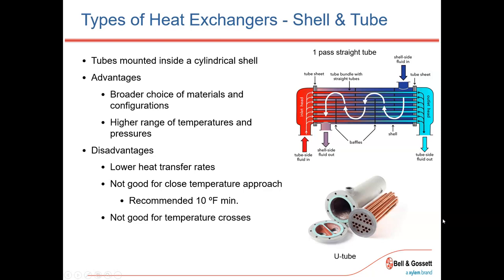And so it's great in that as you have extreme temperature differences between, let's say, your coil side and your shell side, the expansion and contraction rate won't match up, but that tube bundle is almost floating in there. So actually, take a step back. There are two different sides. You have the fluid that's within the tubes, and then you have the fluid or the steam that's on the outside of the tubes. So we have the shell side, which is on the outside, and then you have the tube side inside. So if you have extreme temperature differences, it's nice that you're really only fixed on one end, and you can get that fluctuation and give without doing any sort of damage to the unit.